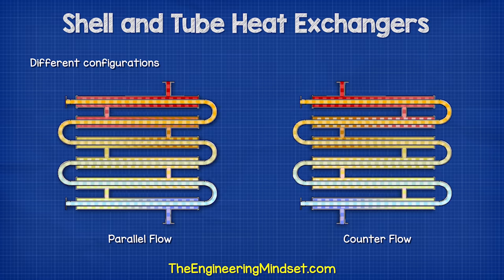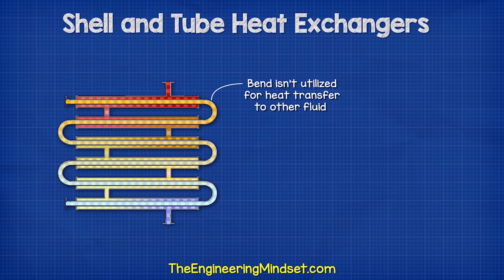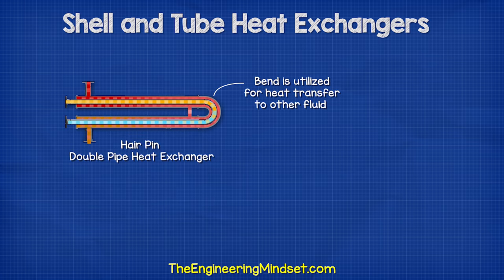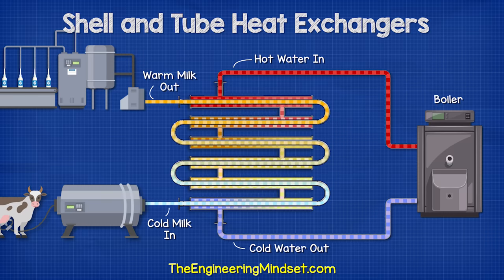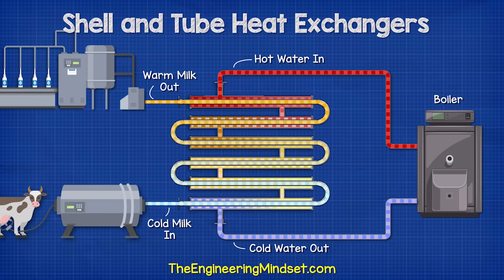The different configurations result in different temperature profiles and heat transfer. In this design the bend at each end isn't utilized for heat transfer and heat can be wasted here. However, manufacturing this heat exchanger is cheaper and easier. Other designs, like the hairpin type heat exchanger often found in oil refineries, encapsulate the bend to fully utilize the surface area for heat transfer. This version normally uses multiple tubes to maximize the surface area and thus increase heat transfer, although this will also increase the resistance. These are a fairly simple heat exchanger design and are very common, particularly in food processing as well as pharmaceutical production.